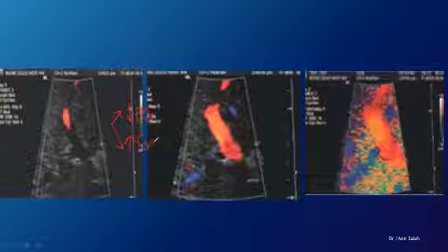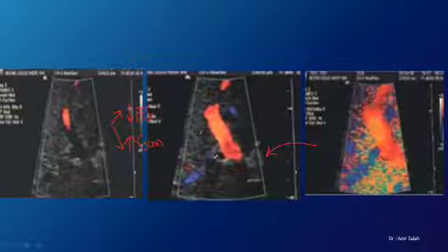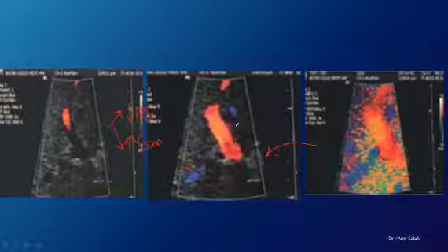Then we have two possibilities why there is no color flow here in your color box. And what to do? I would suggest that you at first increase your gain until there is color flow inside and outside like this. There is this aliasing, and then you start to gradually decrease it until the color flow is just in your blood vessel. Then you do what? You start to decrease the PRF until there is sufficient variations in the color to match the velocities, as we've said earlier.